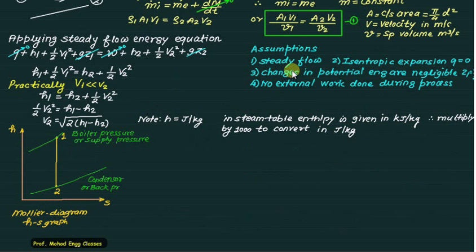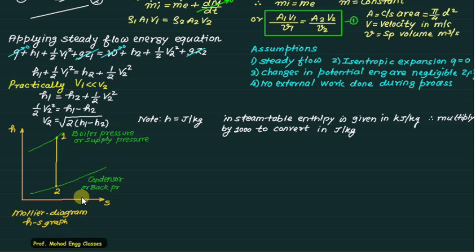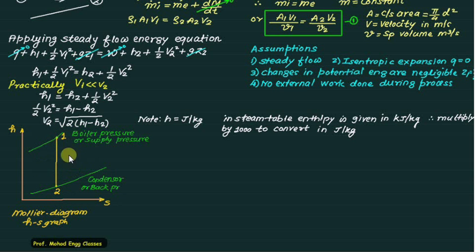Isentropic expansion means: before the nozzle we have a boiler supplying pressure, and after the steam turbine we have a condenser developing back pressure. Expansion takes place from state 1 to state 2. On the Mollier diagram, enthalpy versus entropy, the isentropic expansion process follows a vertical line so entropy is constant and h1 minus h2 is the isentropic enthalpy drop.